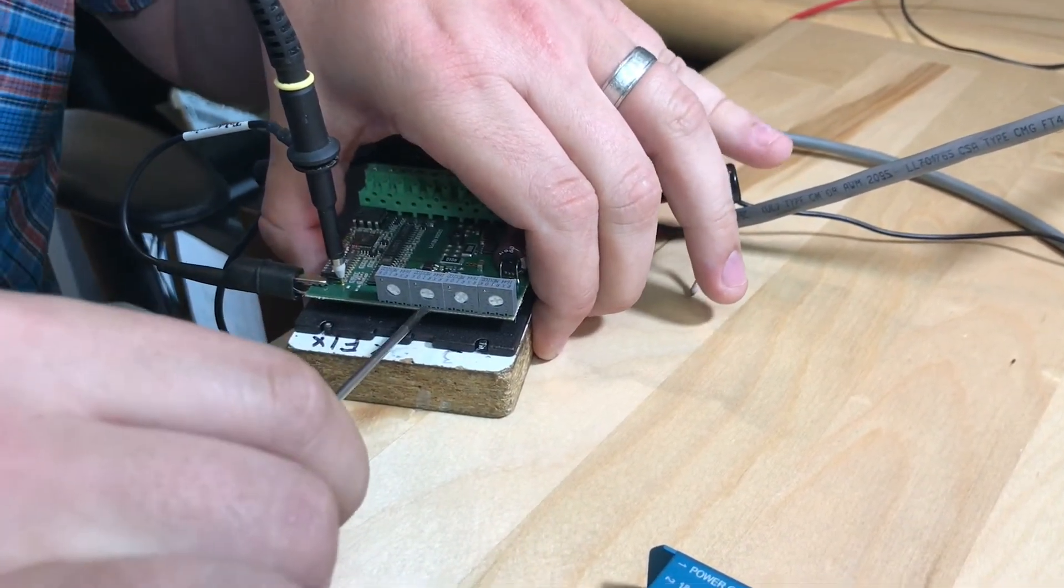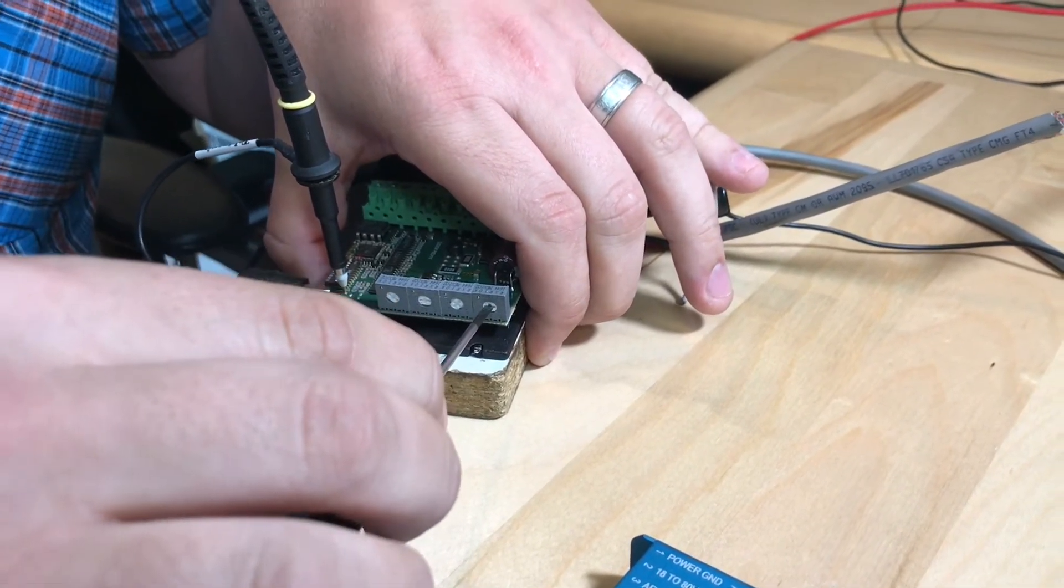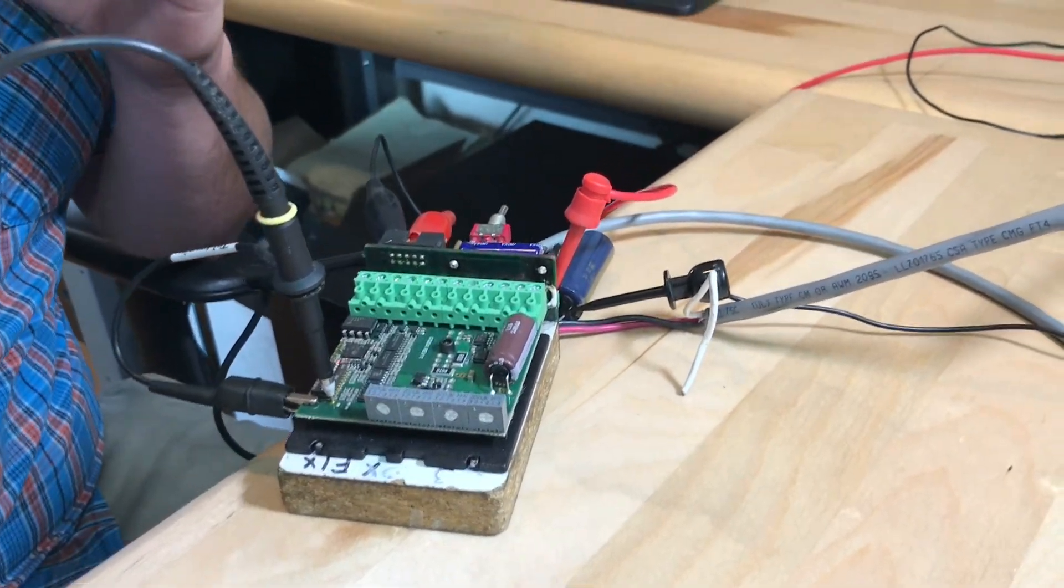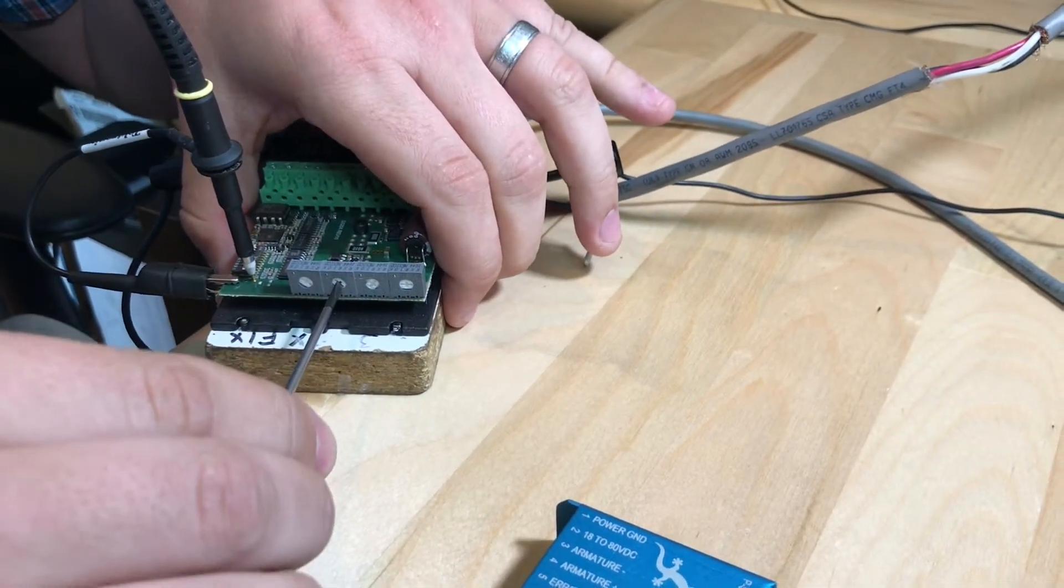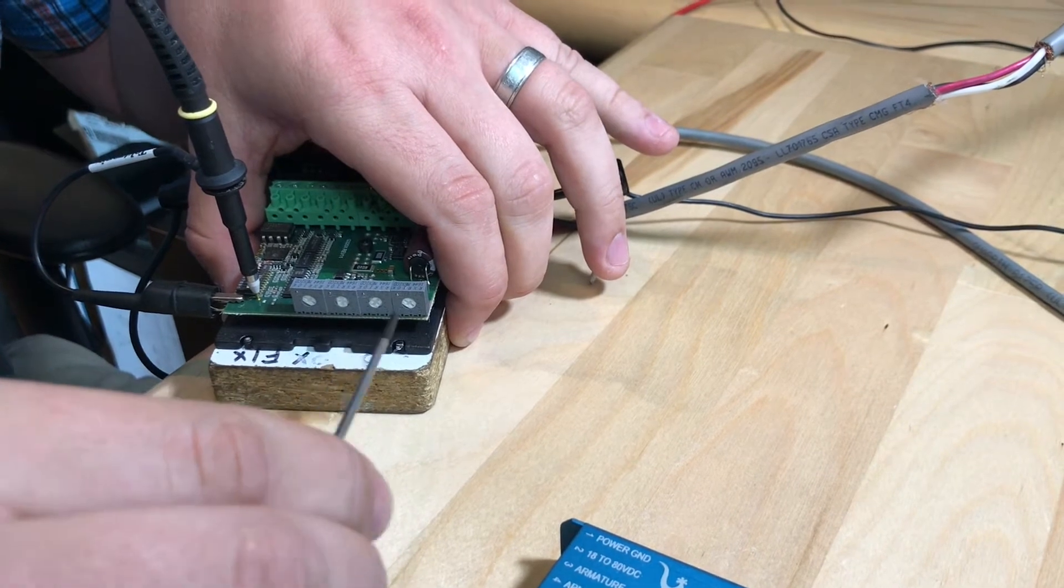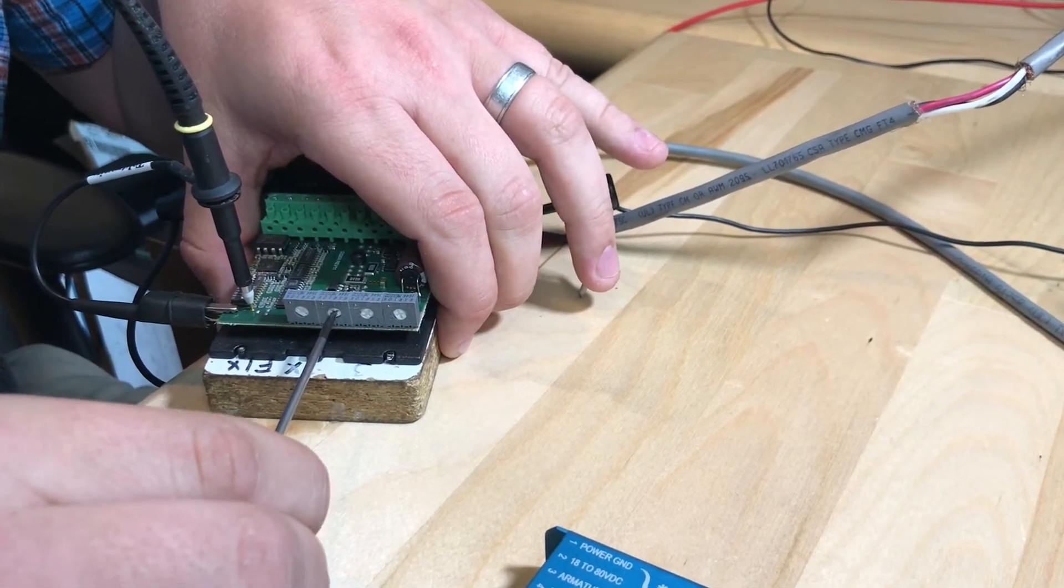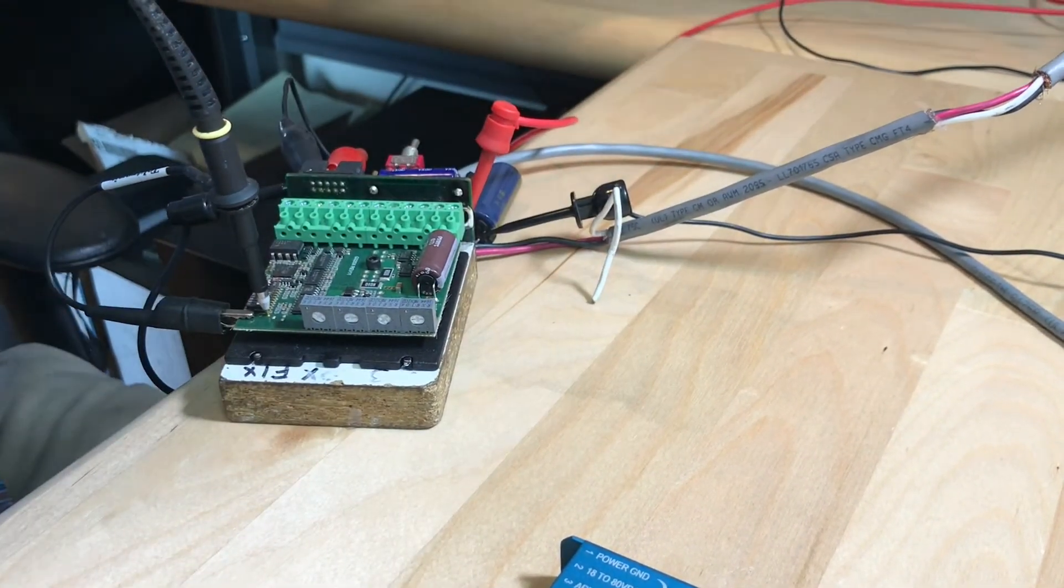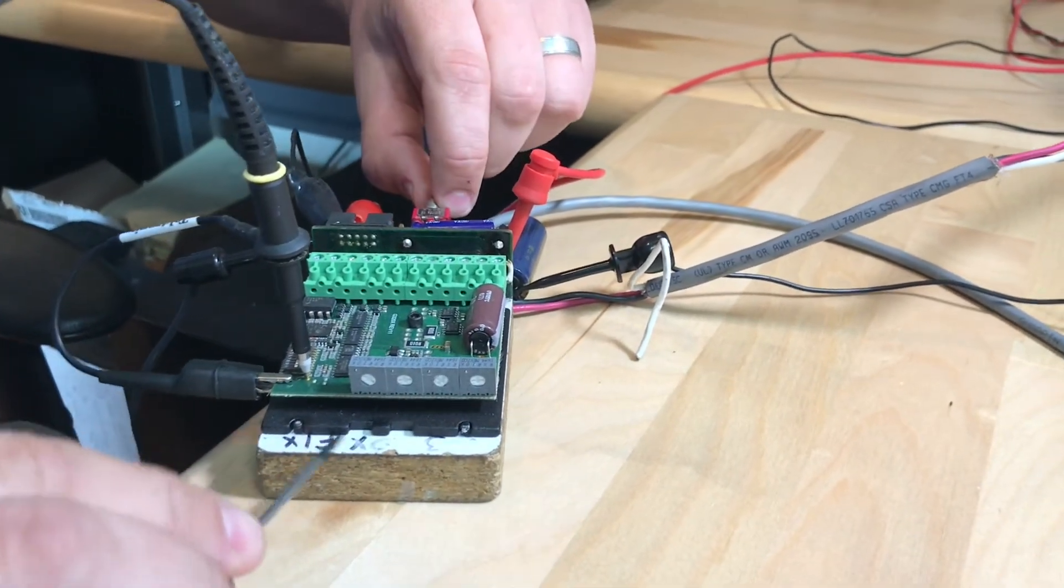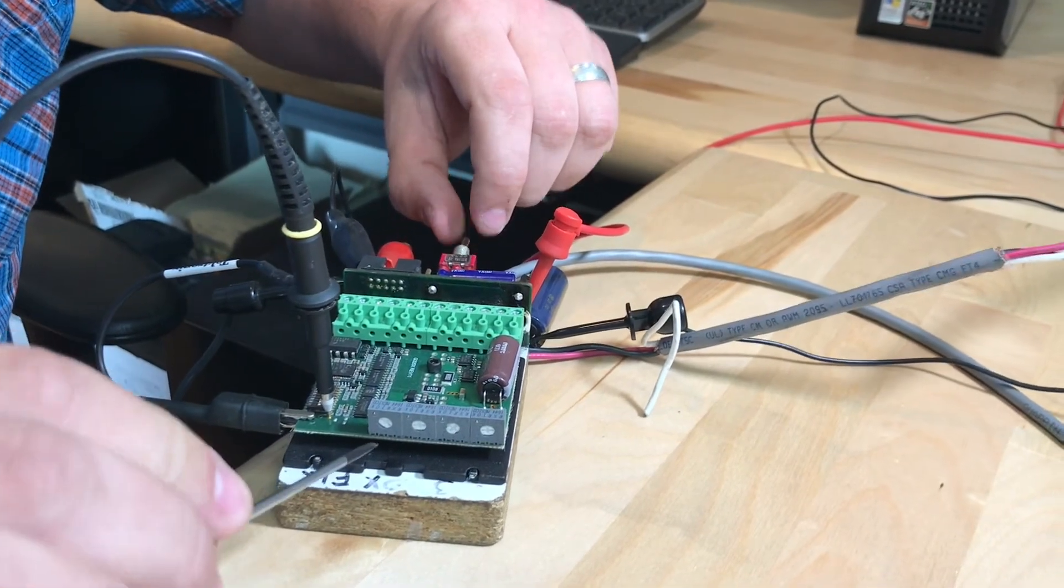Turn your P and your D to about nine o'clock. Remember, the D always has to lead the P. When you adjust it, adjust each one slightly going up until you get a good middle ground, and then you can tune from there. I'm going to reset the drive. This is all of them at about nine o'clock with I turned off, so you can see it's not doing what it's supposed to do.